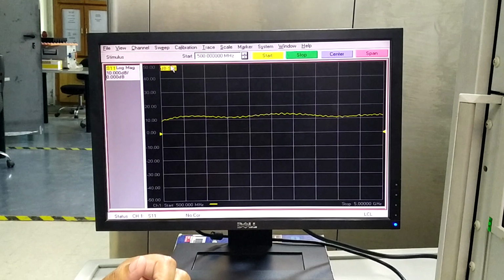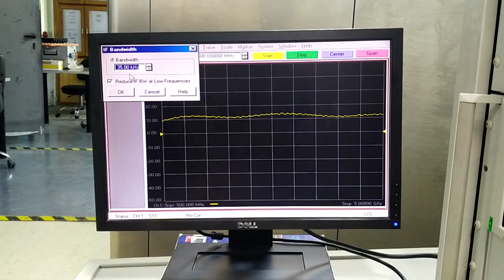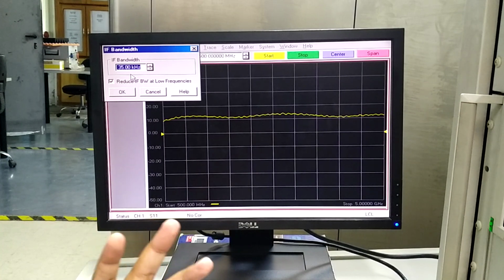The next option is the IF bandwidth. Here it's set by default to 35 kilohertz. This IF bandwidth is very important also because, as we discussed in class, in the architecture of the VNA, when the signal is received by the measurement channel and is down converted, there is always an IF filter, and that IF filter has a particular bandwidth, so you can select the filter bandwidth and then post process it. Here the default value is set to 35 kilohertz, so we keep it like this. This IF bandwidth plays a much more crucial role in spectrum analysis. In a spectrum analyzer it has a much more crucial role, but for the vector network analyzer, we keep this as the default value of 35 kilohertz.